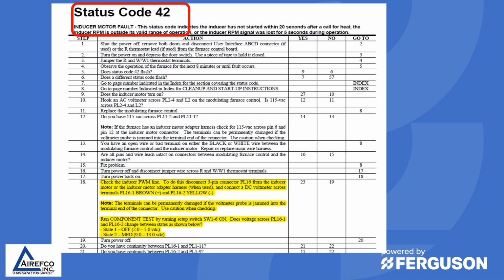This particular code 42 is an inducer motor fault, which is an ECM motor. You will have steps that they want you to go through to try to determine what the problem is, and by answering yes or no, they direct you to the particular step that you need to be checking.